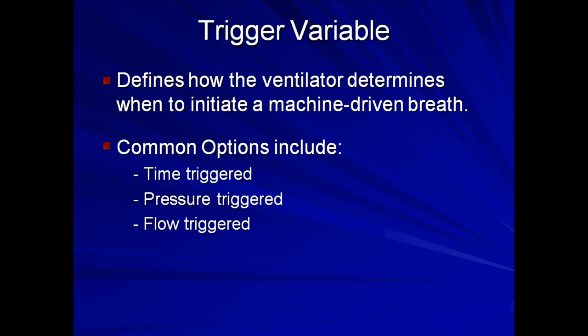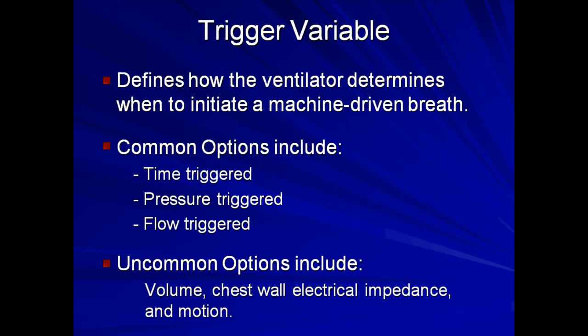For patients with spontaneous respirations, this variable may be set to either pressure triggered or flow triggered such that the ventilator delivers a breath when either a threshold negative pressure or a threshold degree of flow is detected. Both pressure triggered and flow triggered ventilation are equally effective and there is rarely an advantage to switching from one to the other, with the exception of patients with COPD who may do better with a flow trigger. Triggering options used less frequently include volume, chest wall, electrical impedance, and motion.